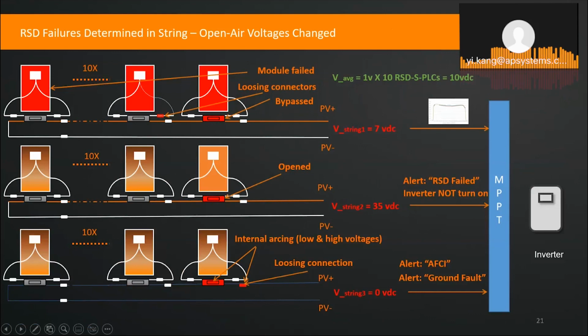For SMA also, another thing you need to pay attention to is they set up exactly following the SunSpec alarming requirement, which has a minimum of 6 modules. And when they made the program, the starting voltage, I think, is 6 volts. So if your string, like this happens very often on residential jobs, only has 4 panels per string, and you put it into one of the MPPTs, that will alert and not turn on the SMA, because they know you are lower than the starting voltage. They will alert you and hold it there, not turning on the inverter until you reach the starting voltage limit. Be aware of that. I'm not sure if Fronius has this function or not.